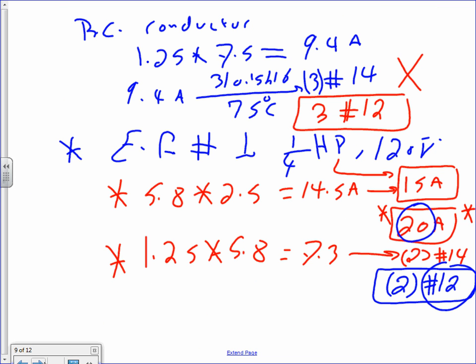So let's look at the conductor. Branch circuits, the same thing. You take 1.25 times 7.5, which gives you 9.4. 9.4 gives you number 14 conductor. What did they say about using number 14 in a commercial building? No. So what do we flip it to? Number 12. Why 3 conductors? 3-phase.